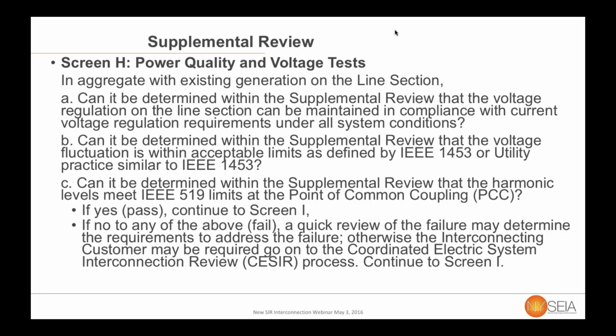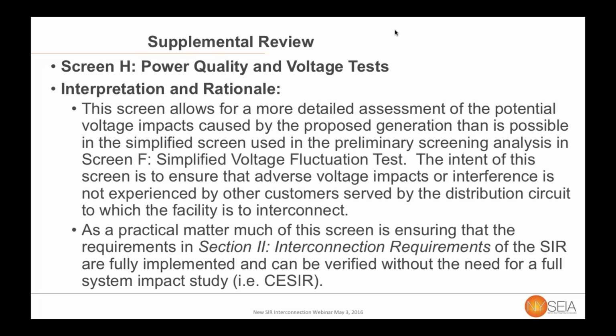The last two screens, power quality and voltage, look at three pieces. It says, can you determine without the need for a CESIR that voltage regulation will be fine? That flicker will not exceed the limit set by the new IEEE standard 1453 or similar standards, and can the harmonic injection be held within the limits of IEEE 519? Again, this is a screen that looks at more detail than that simplified voltage test does, and mainly as a practical matter implements requirements that are within that Section 2 interconnection requirements.